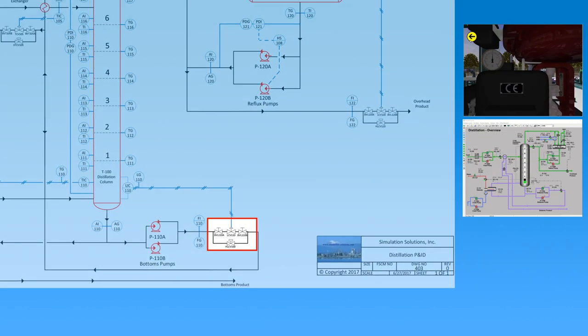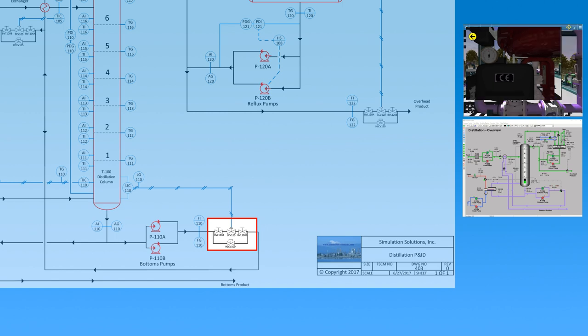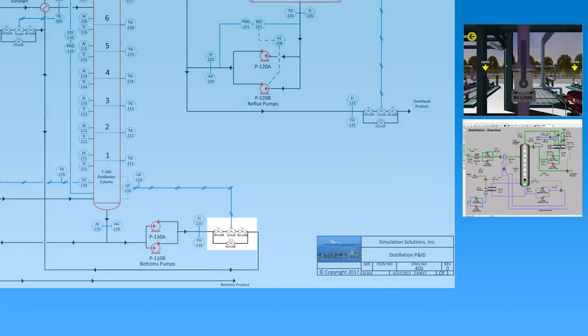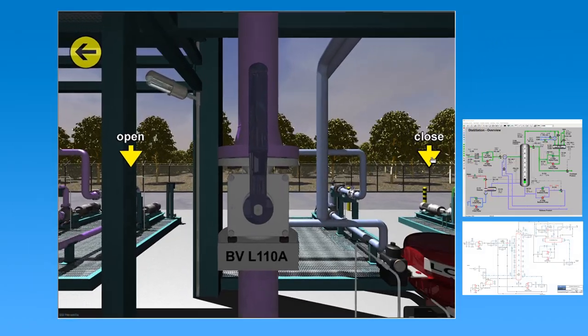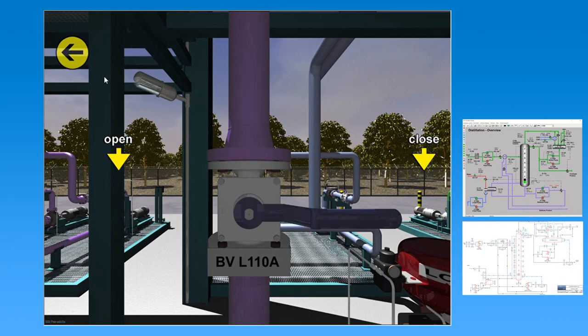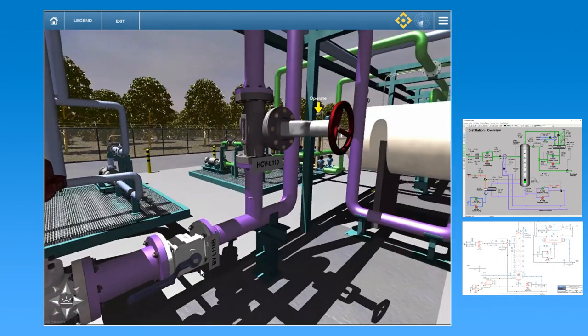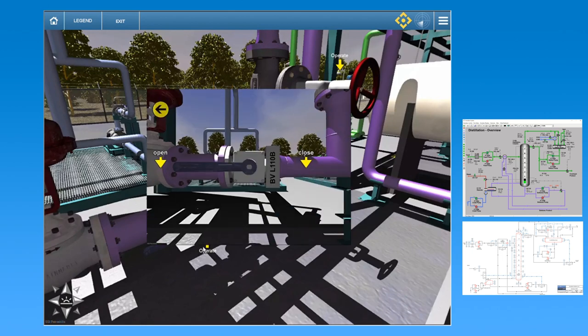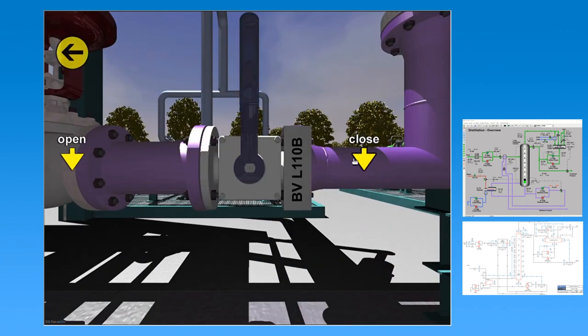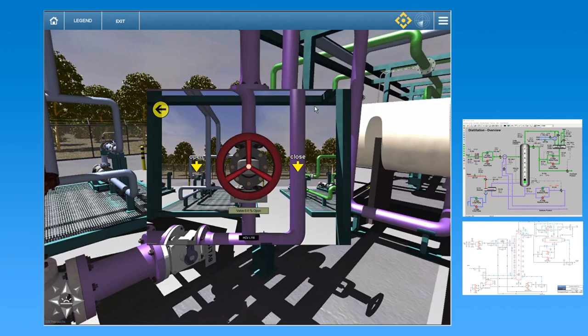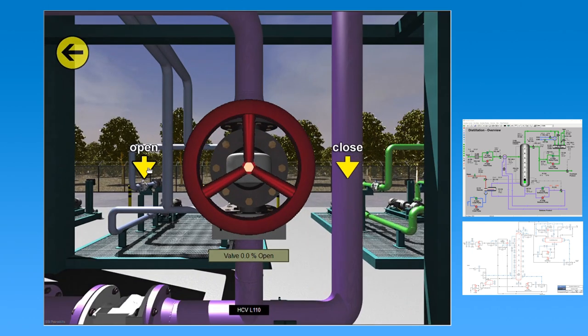A quick look at the piping and instrumentation diagram shows that the control valve in question is LCV 110, which has a bypass valve and block valves upstream and downstream to allow for isolation if needed. The outside operator opens the bypass and isolates the control valve. The console shows flow at the pump's discharge and the tower's level stabilizes.